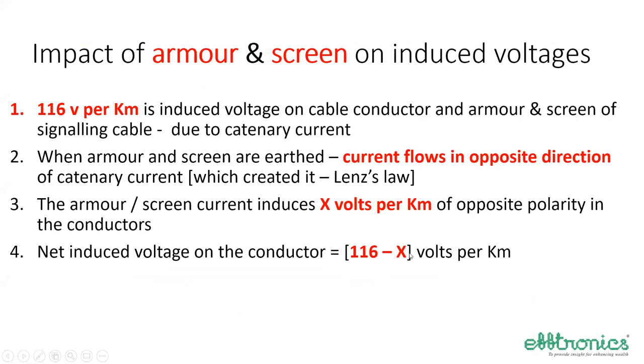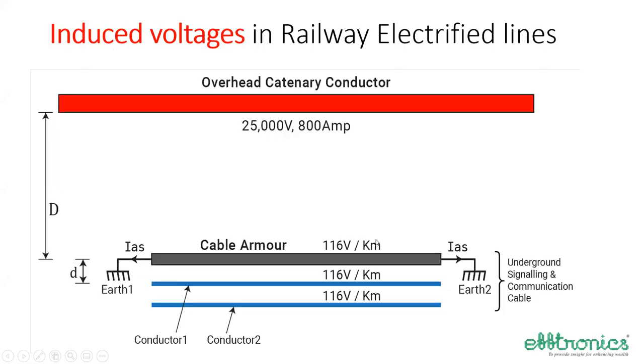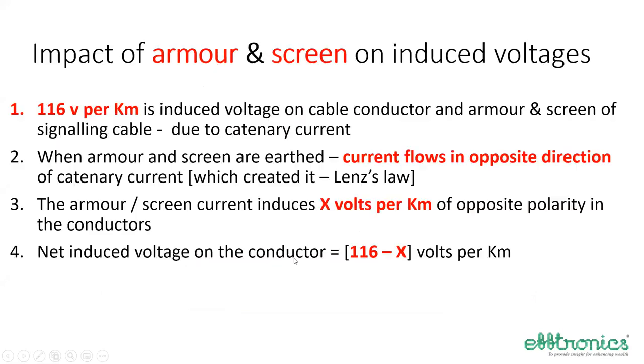This X, we have to make as large as possible. How can we increase the X? Number one, by having good earth. Number two, by having continuity of the armor. When we are laying a cable, let us say a 6-quad cable of 5 kilometers or 10 kilometers, if the armors are not connected and earthed at the end of each cable cut, then the effectiveness of the screening is lost. These are the mistakes done while installing.